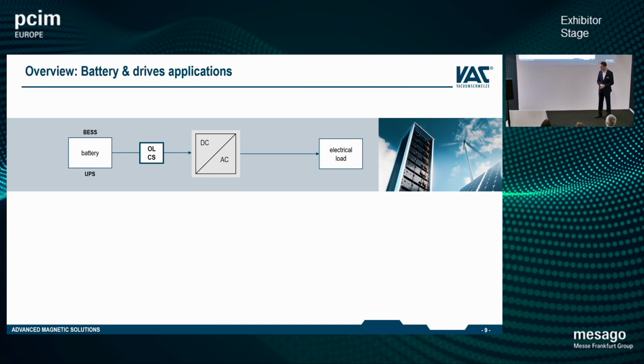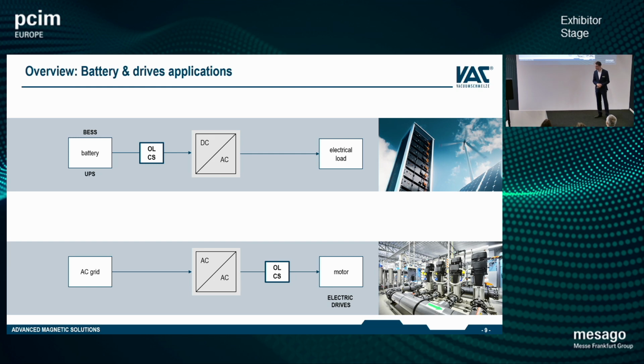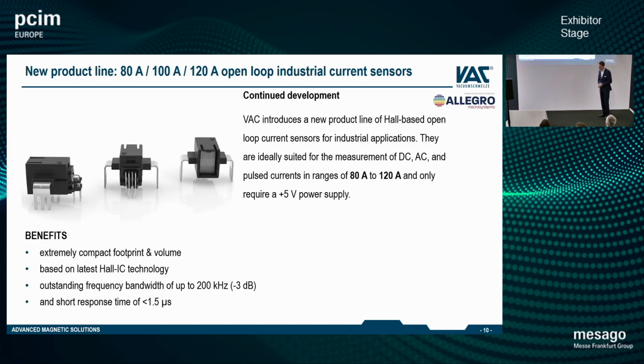Another potential scenario is for electric drive applications. There you have an AC input, for example a 3-phase AC grid input, and an AC-AC inverter. The open-loop sensor is located between the inverter and the motor in this application example. We are talking about application classes in the range of 30, 40, 50 kilowatts, for example, where these sensors are suitable.